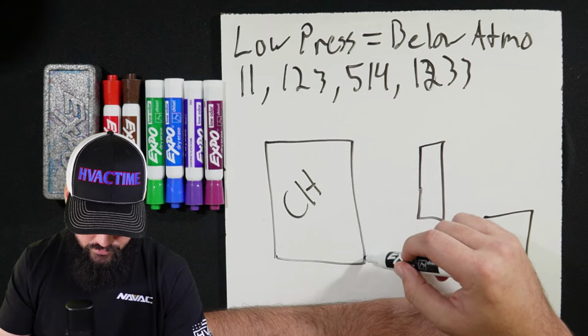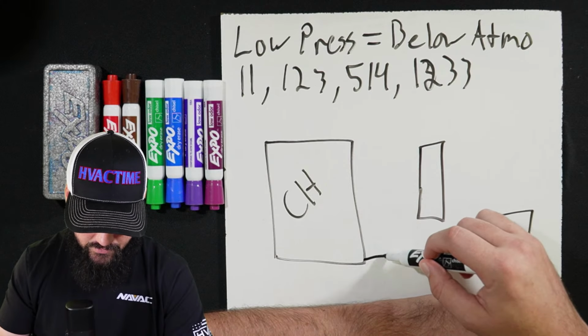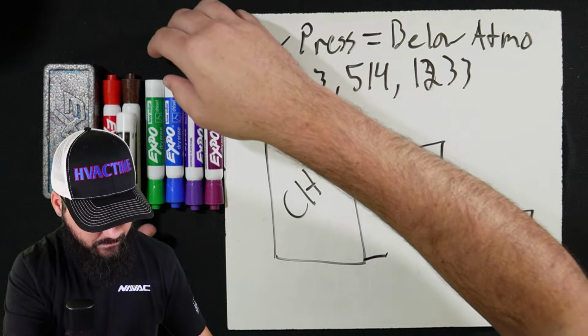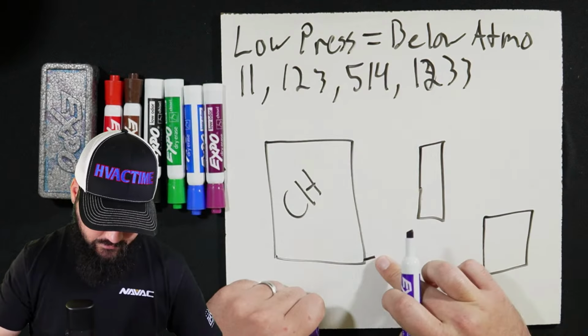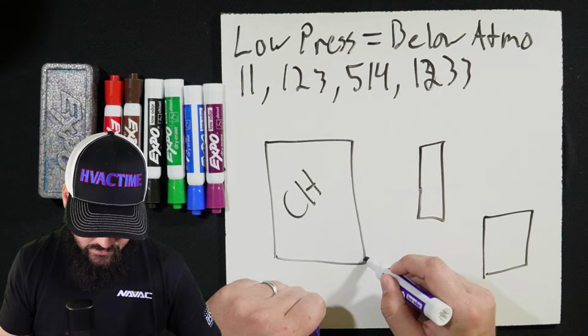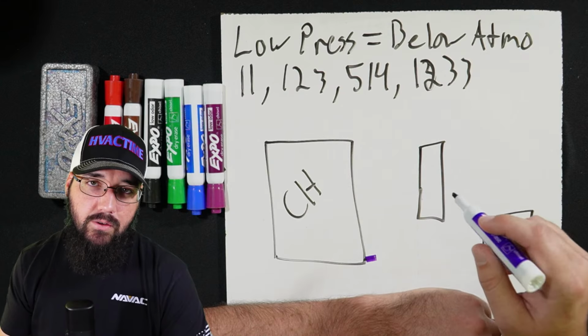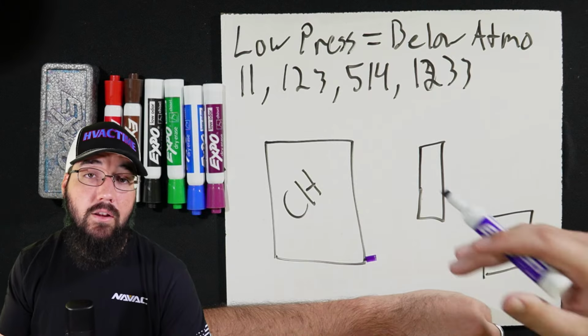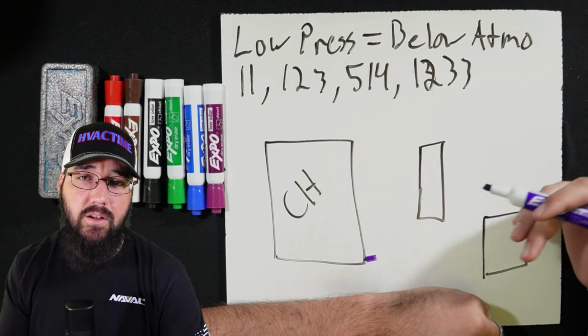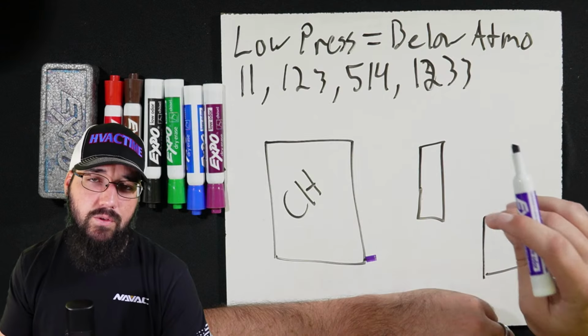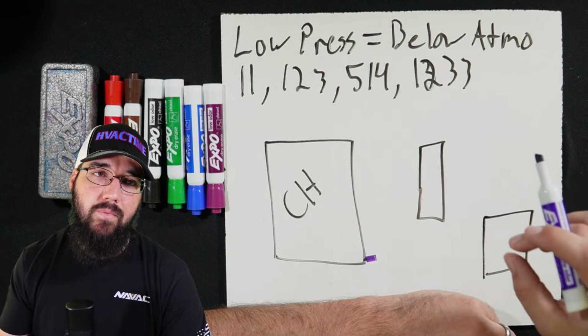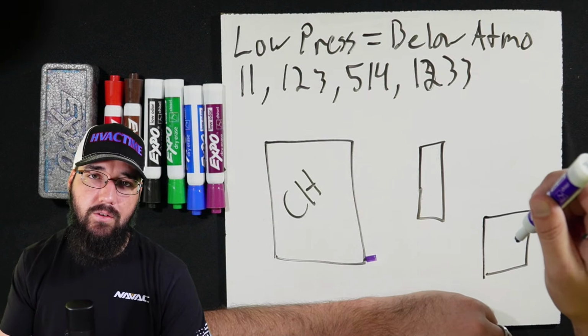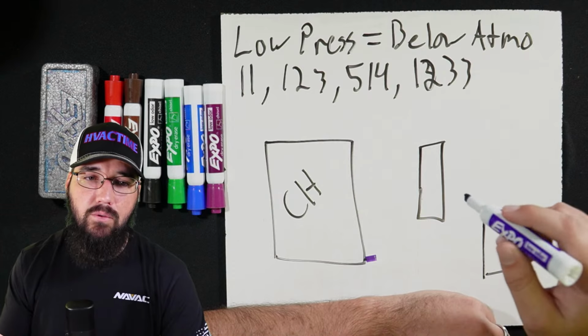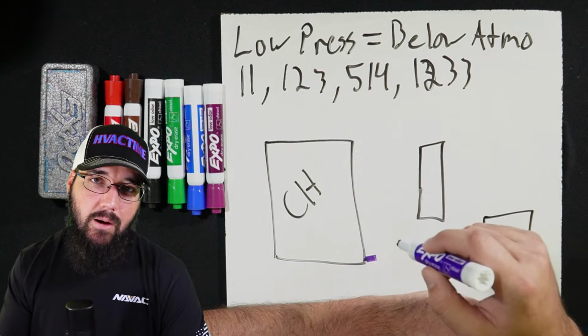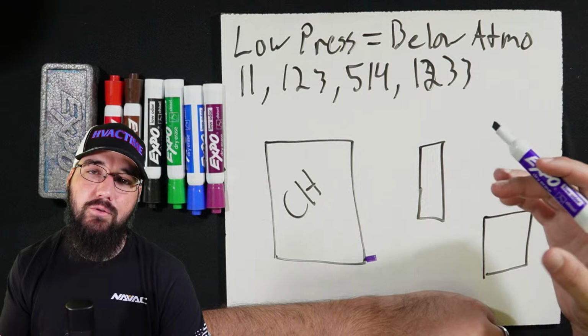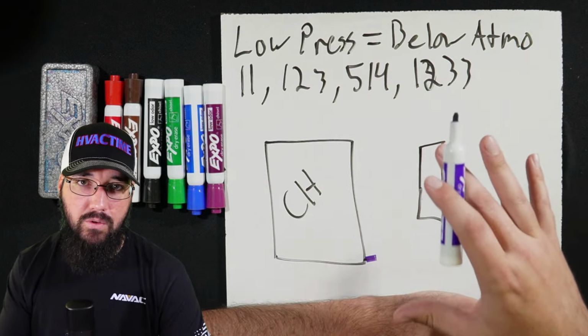What is important is we're going to pull from the, here, let's do it this way. We're going to pull liquid from the bottom of the chiller. Now, typically, these low pressure machines are, I say typically as if they're not, they're centrifugals. All of them that I'm aware of on the market that I've ever seen, ever heard about, they're centrifugals. And with these particular designs, specifically being water-cooled machines, you're going to have majority of the refrigerant in the evaporator once it shuts down. That refrigerant goes into the evaporator and stacks there in most cases.